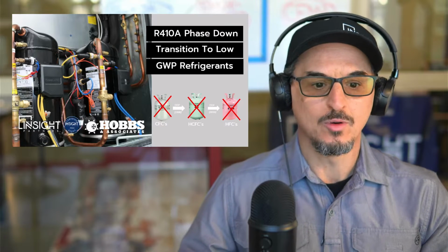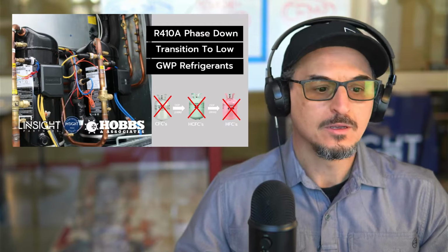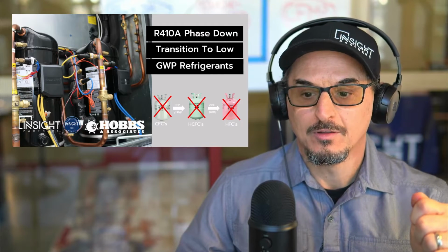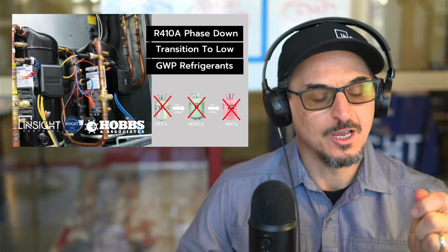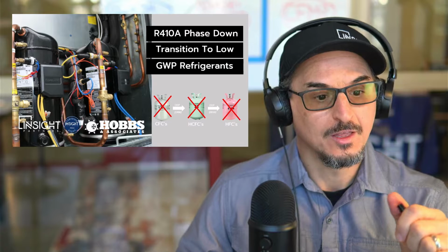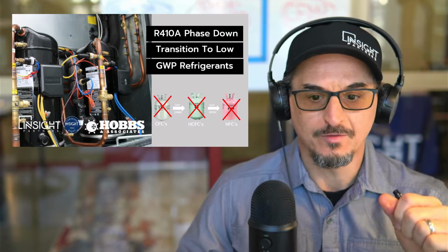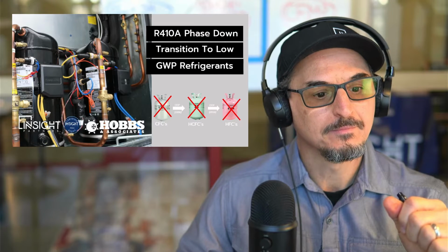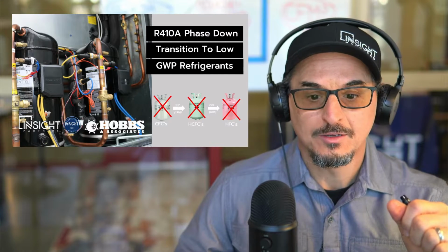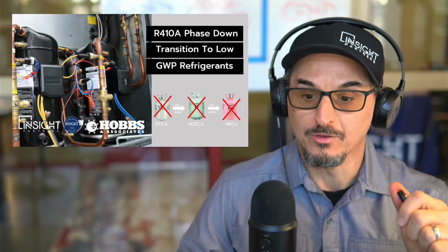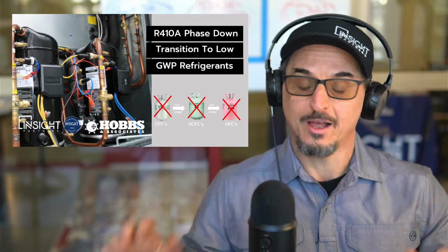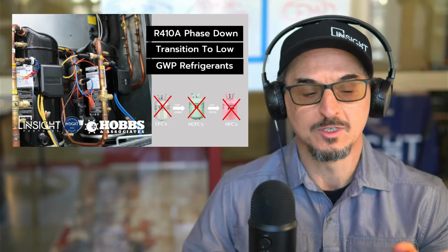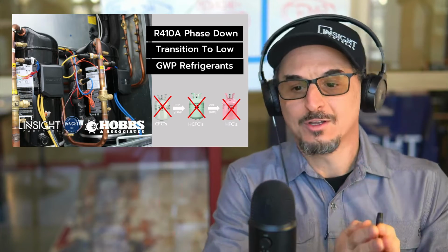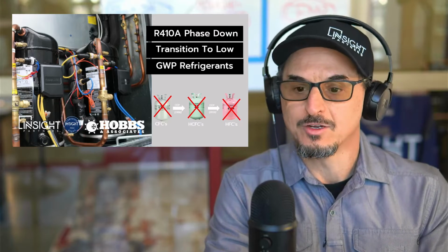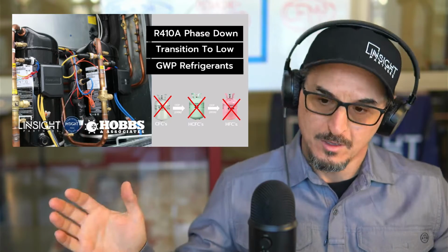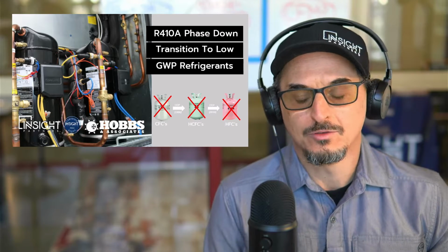Basically the dates are as follows: for equipment manufacturing deadlines, the national transition to GWPs lower than 700 for chillers and air conditioning systems, non-VRF, is 1/1/25—January 1, 2025 is when that all goes down. The national transition for VRF systems is 1/1/26, so VRF gets an extra year. I don't know why—I guess it's more complex to change the refrigerants in those systems, I'm not really sure, but they get an extra year. So after 1/1/25, you cannot ship a manufactured piece of equipment with a GWP refrigerant over 700, and the same goes for VRF on 1/1/26.